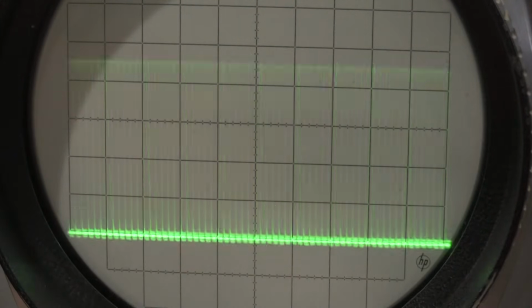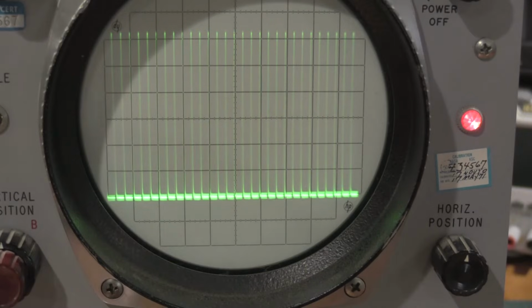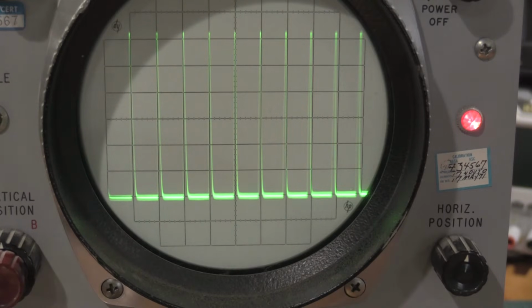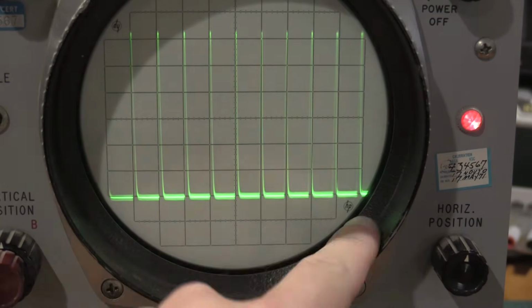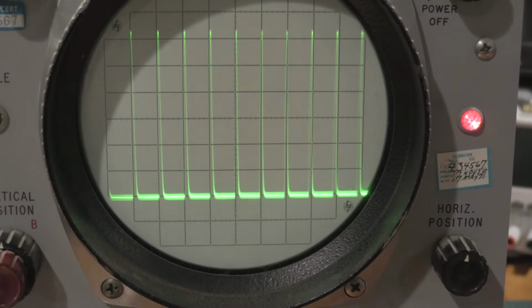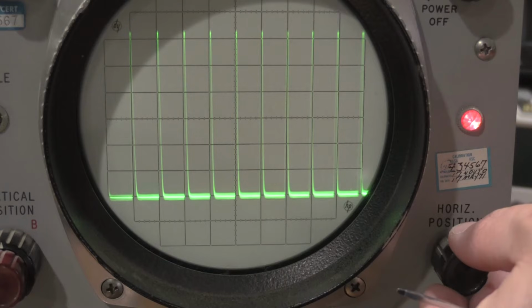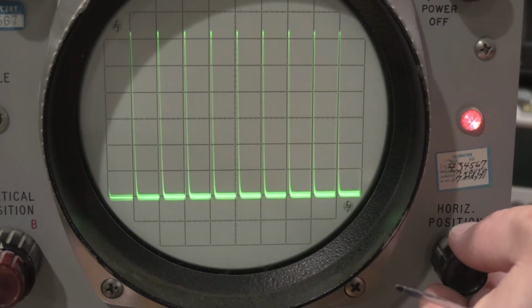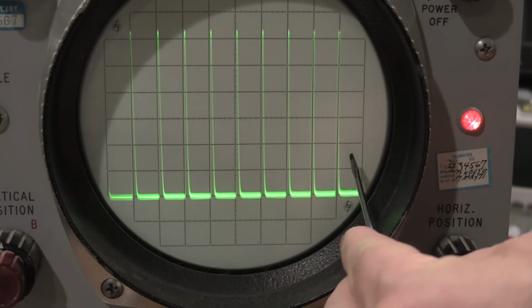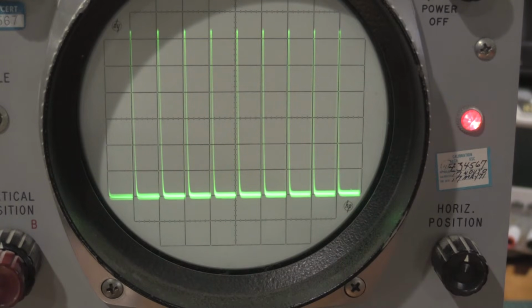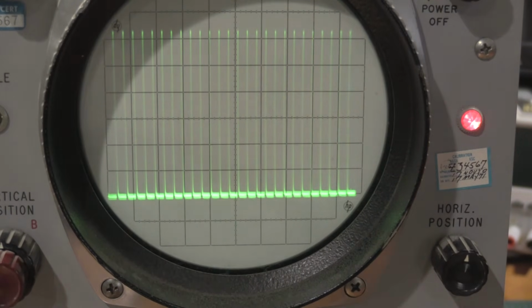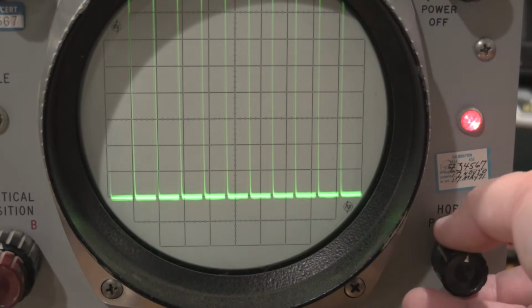Let's check 20 microseconds. I found out when the scope was doing this, my switch wasn't latched all the way, so that's going to cause problems. So we still hit in spec, and I'm still 2.5% fast, but now this range is running a touch slower. Using a camera as the guide, we'll judge the time marks from here to here, 10% and 80%, the same way a Tek scope would do it. Now this one's only 1.3% fast, so on the 20 microsecond range we get even better. What does 50 do? As the time marks speed up.